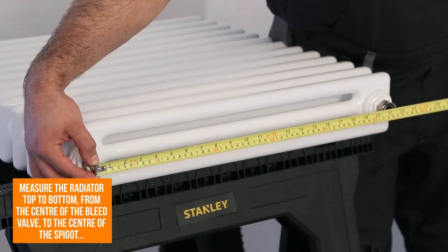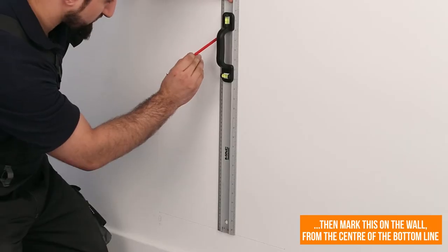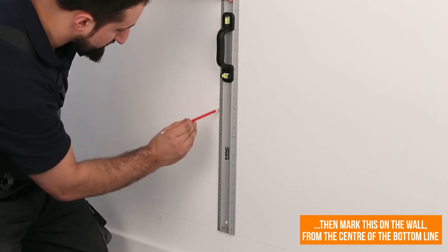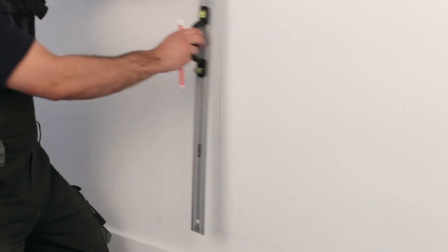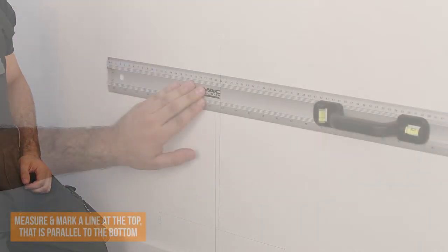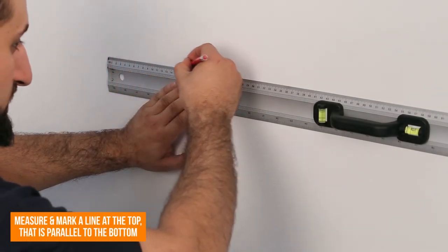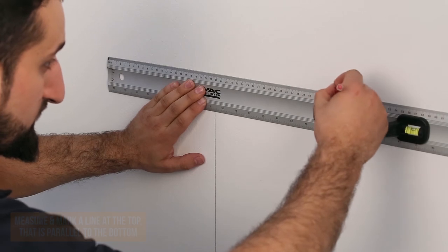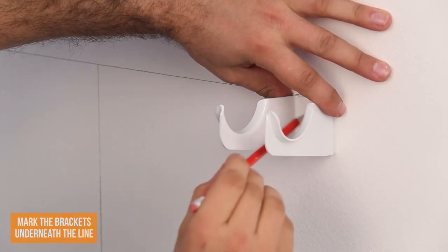Measure the column designer radiator top to bottom from the centre of the bleed valve to the centre of the spigot, and then mark this on the wall from the centre of the bottom line. Measure and mark a line at the top which is parallel to the bottom — this is where your top brackets will be situated. As with the bottom set, place the top of the bracket below the line and mark the holes ready to be fixed.